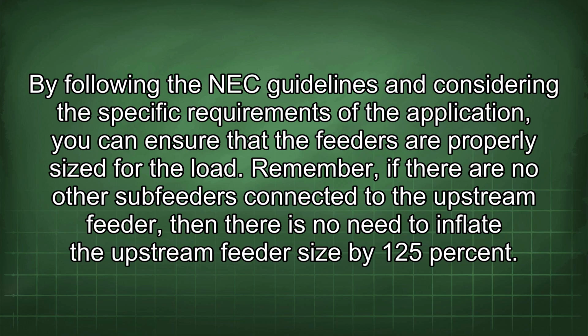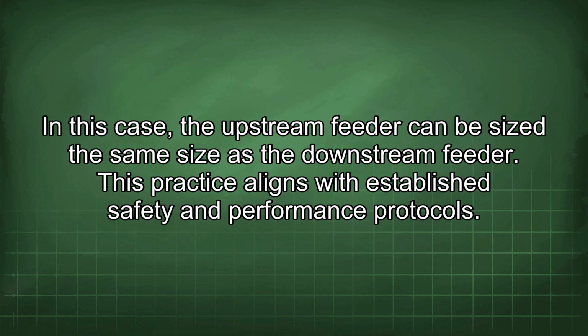Remember, if there are no other subfeeders connected to the upstream feeder, then there is no need to inflate the upstream feeder size by 125%. In this case, the upstream feeder can be sized the same size as the downstream feeder. This practice aligns with established safety and performance protocols.